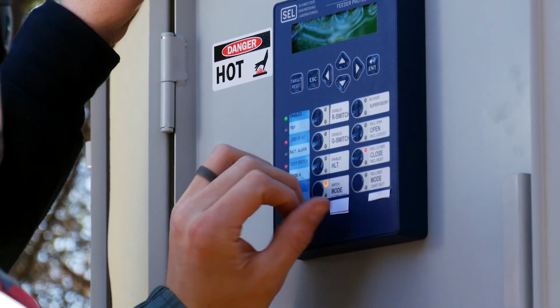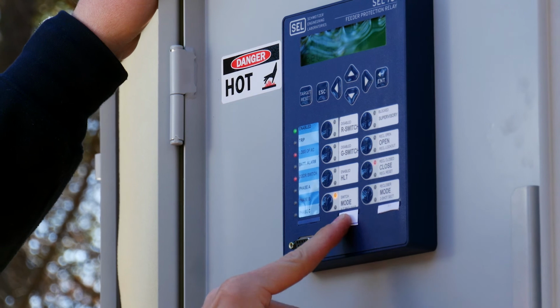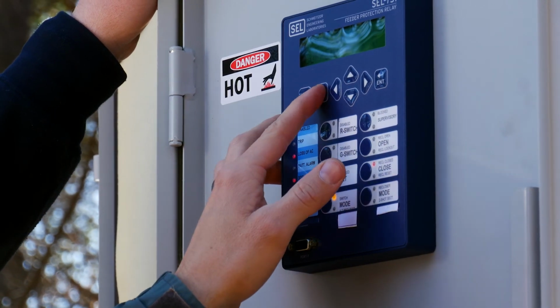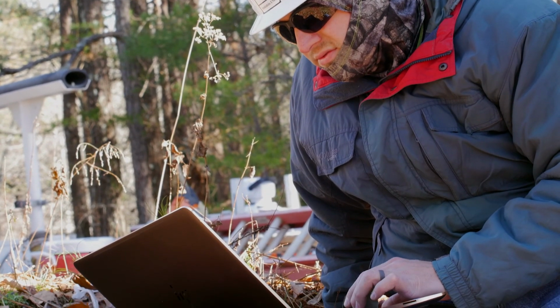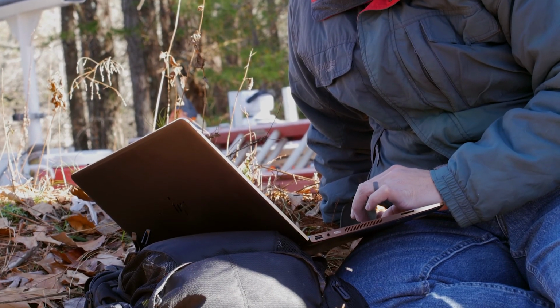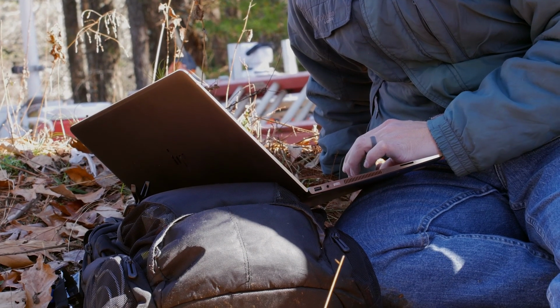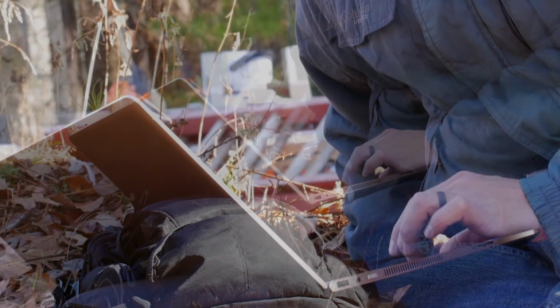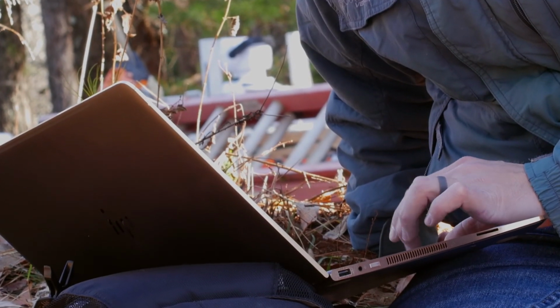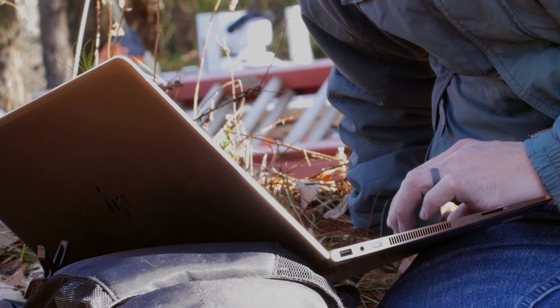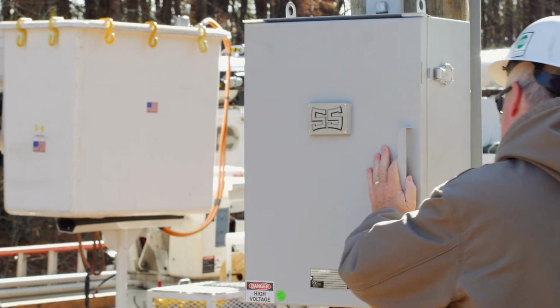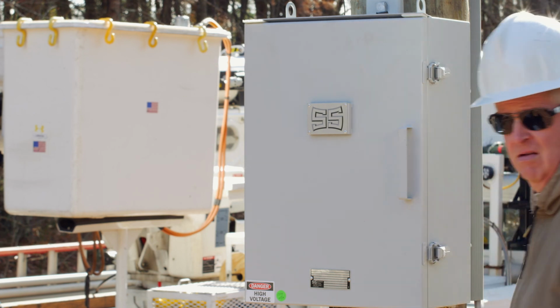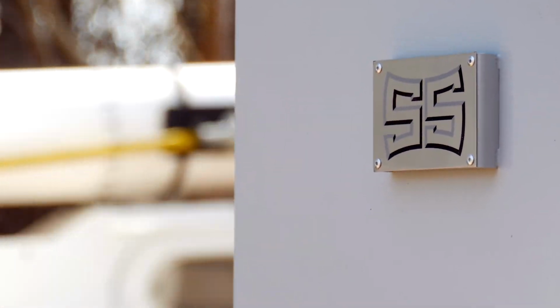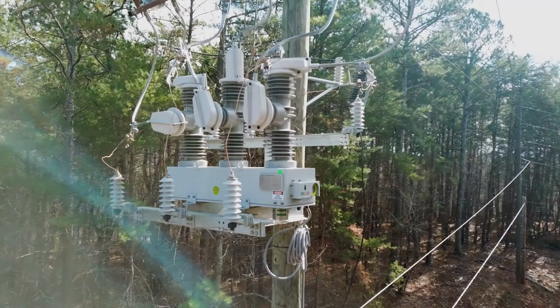If a SCADA system is present, most utilities will opt to make that connection at this point during the installation. Prior to closing in the disconnects and performing any device testing, it is suggested to place the relay in non-auto reclose mode. When the utility is ready to perform a final point-to-point checkout, the disconnects can be closed while leaving the bypass in place. This will allow for trip close as well as voltage testing without the possibility of disrupting power to the customers on the line. At the completion of all desired testing, make sure the recloser and relays are in the normal state. The utility can now remove the bypass and the equipment is live and ready for use.